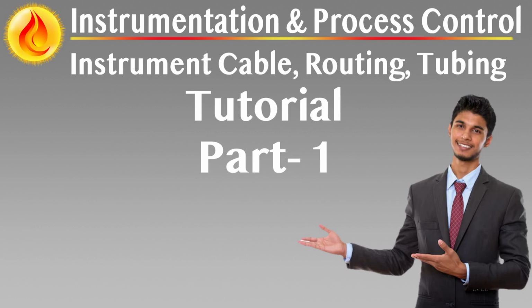Digital and video cabling. Systems requiring digital or video signal transmission, such as microprocessor-based instrumentation or CCTV, should use appropriate media based on bandwidth and distance: twisted pair, coaxial, or fiber optic. Fiber optics are preferred for high EMI environments, lightning exposure zones, and long-distance communication between central and auxiliary rooms.